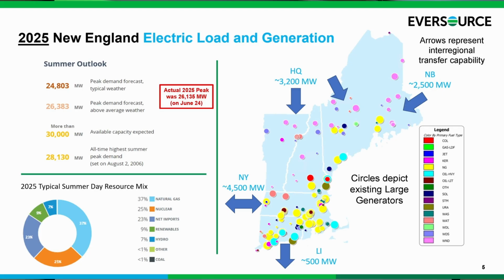This is something I'll touch on again later, but the major load pockets—I gave you the overall New England-wide numbers—are, as everyone could probably guess, Boston and Southwest Connecticut. Generally, on a typical day, there's not a lot of generation internal to the Boston load pocket, so you'll normally see flows into Boston and then southwest into Southwest Connecticut. That's generally how the power flows on an average day. For example, you can see the large concentration of yellow circles in Rhode Island, north of Rhode Island—those generators are often flowing into Boston because it's the largest load pocket.